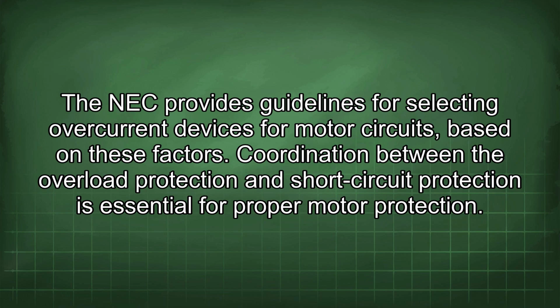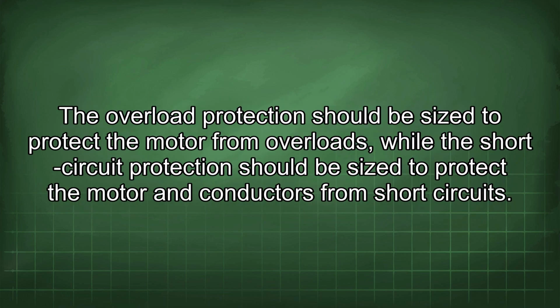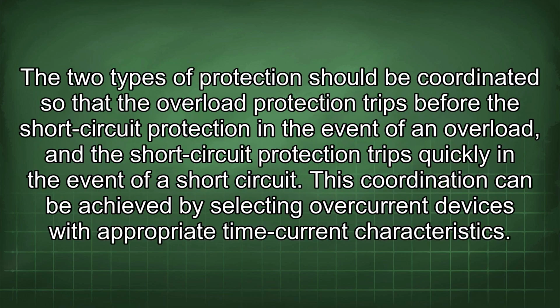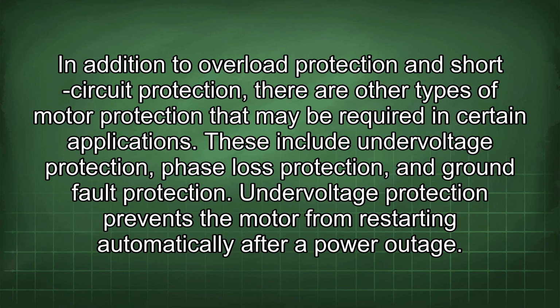Coordination between the overload protection and short circuit protection is essential for proper motor protection. The overload protection should be sized to protect the motor from overloads, while the short circuit protection should be sized to protect the motor and conductors from short circuits. The two types of protection should be coordinated so that the overload protection trips before the short circuit protection in the event of an overload, and the short circuit protection trips quickly in the event of a short circuit. This coordination can be achieved by selecting overcurrent devices with appropriate time current characteristics. In addition to overload protection and short circuit protection, there are other types of motor protection that may be required in certain applications.